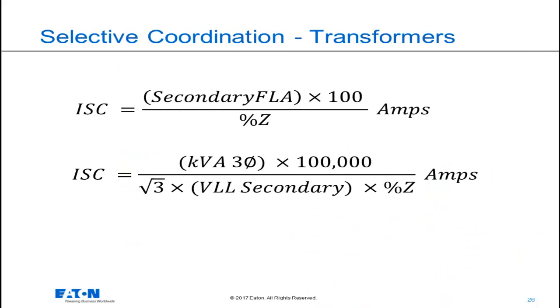These are the two equations that you need to know. The first equation is useful when you have the nameplate of the transformer in front of you. Usually, the secondary full load amps is printed on the nameplate, as is the percent impedance. The second equation is useful when you are provided with the kVA, voltage, and percent impedance of the transformer during the design phase. The connection of the transformer primary and secondary windings, meaning delta, wye, or other, does not impact these calculations.